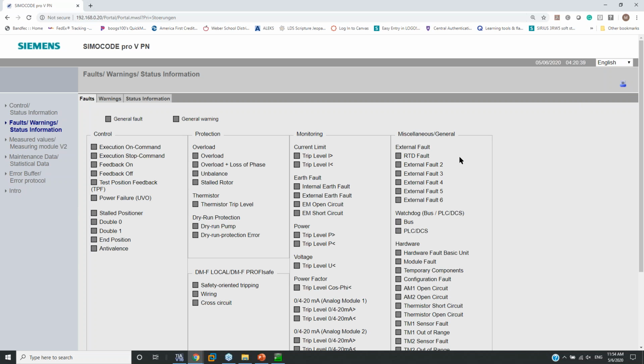RTD fault. So you guys have a little web page and OPC-UA tag publisher with it. It automatically updates and gives you those external faults. Now bear in mind that it only allows 10 characters. You can't put in some elaborate explanation for it. Your max is 10 characters. But now you can go into these external faults and give them actual names, so that your operator knows exactly what's faulting, or gets some type of error with it instead of it just saying some external fault. That's the power of SIMOCODE.